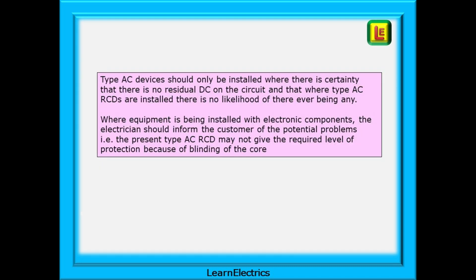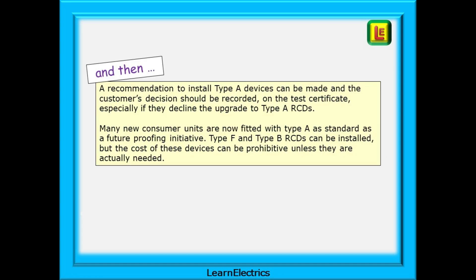Type AC devices should only be installed where there is certainty that there is no residual DC on the circuit and no likelihood of there ever being any. Where equipment with electronic components is being installed, the electrician should inform the customer of the potential problems — that the present type AC RCD may not give the required level of protection due to blinding of the core — and recommend installing type A devices, recording the customer's decision on the test certificate, especially if they decline the upgrade. Many consumer units are now fitted with type A as standard as a future-proofing initiative. Type F and type B RCDs can be installed but the cost can be prohibitive unless they are actually needed.